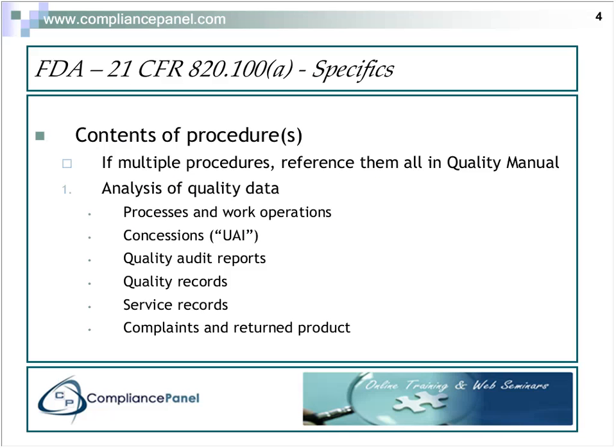820.100(a) gives you a list of what needs to be in your CAPA procedure or procedures. You use the "s" here in parentheses because I find it important to explain to attendees at my seminars and webinars that it is not required that you have one procedure that includes all of your CAPA in it.